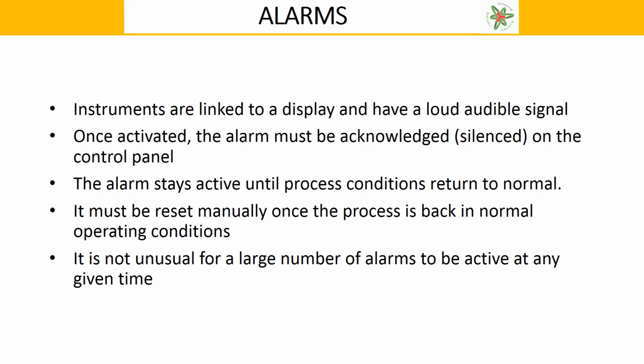All of the instruments that we have in the plant are linked to an audible signal. Once activated, an alarm must be acknowledged or silenced on the control panel. However, the alarm will stay active until the process conditions return to normal. It must be reset manually once the process is back in normal operating conditions. And it's not unusual for a large number of alarms to be active at any given point.